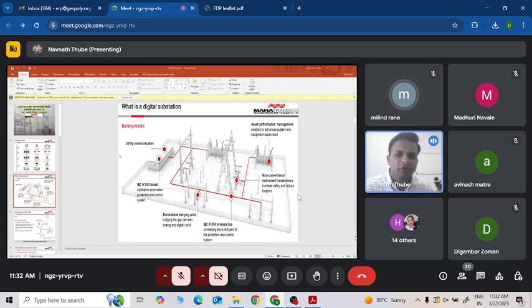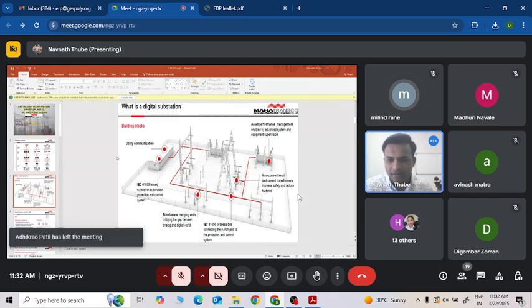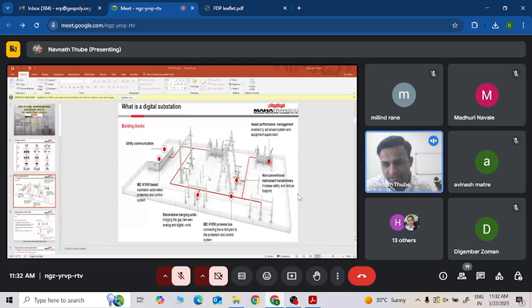The utility communication is our control room, called a conventional control room. All conventional equipment and switchboards are there in a digital substation. Only the communication cables from the equipment or equipment MB to the control room are replaced by fiber optic cable. This is the conventional unit, and this one is the conversion unit, which in simple language converts all analog signals to digital, and through our digital bus the same can be transferred to our utility communication center, the conventional control room, through a digital bus system. This is all based on the IEC 61850 protocol.